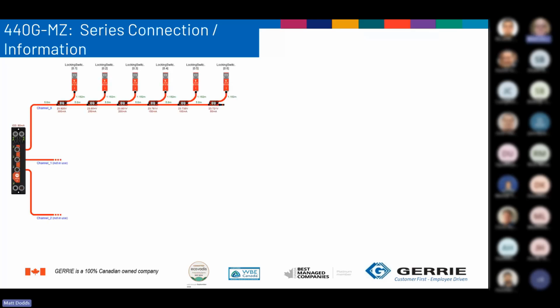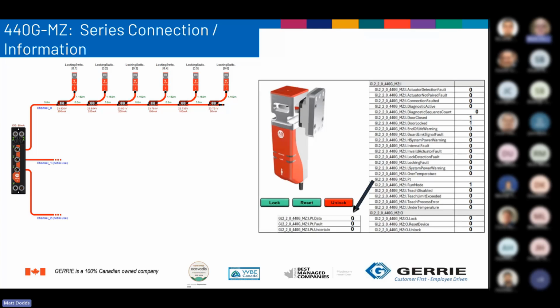And so you want to minimize your wiring even more. GuardLink offers trunk and drop connectivity with T-taps and off-the-shelf M12 cables. The 432 ESIG3 is a complete plug-and-play on-machine block with 3 channels back to GuardLink safety to a GuardLogix safety PLC. When connected to a safety PLC, all of the information for the MZ is available through pre-mapped tags. So again, this is just a screen capture of the information in the PLC.